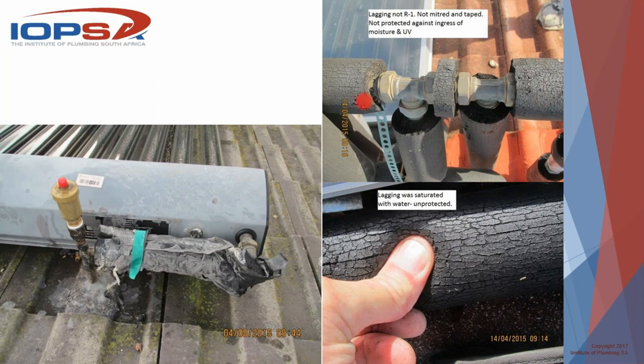But besides that, it's the way that it's been installed. It's not R1 rated. It stops short of all the fittings, so all that heat loss is occurring there. This little piece of lagging is absolutely useless. So this is what we try and prevent. These little upstands over here, when it rains, it's just going to go straight in there between the pipe and the lagging. So this is the kind of thing that is not acceptable.